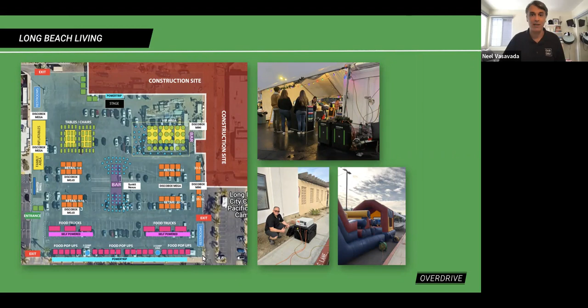Another thing we did was hybridize the generator there. What we did was use our battery systems to actually run those generators at a higher load, because it turns out diesel generators are actually more efficient at higher loads than lower loads. But because of that spike I showed in the last chart, you have to size them for really large loads. So even though there was a generator on site, we made it more efficient by using it to charge batteries, which we then used in this case for the inflatables.